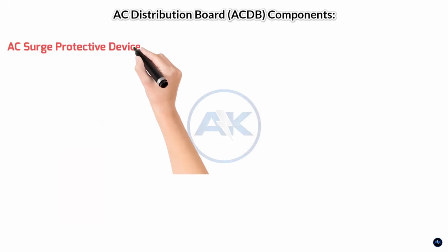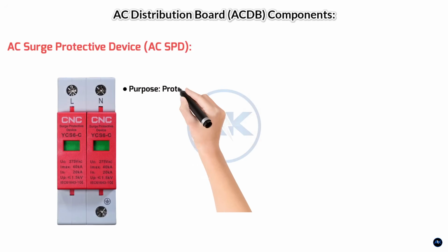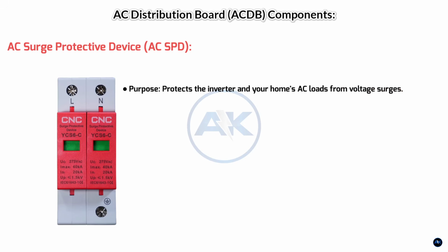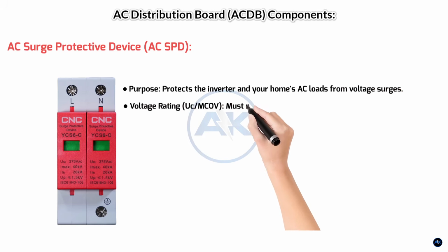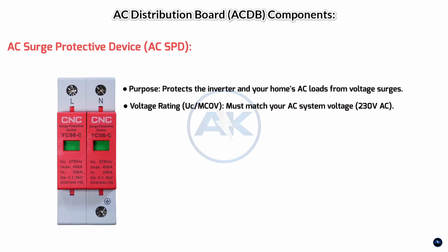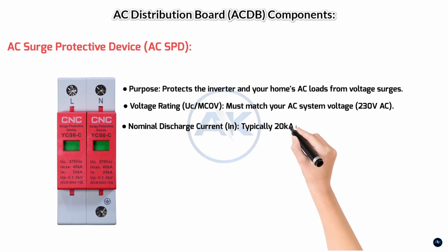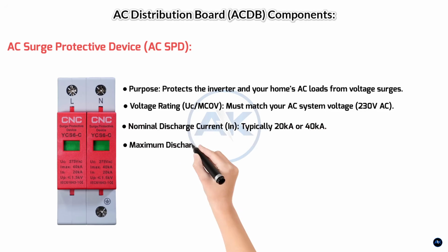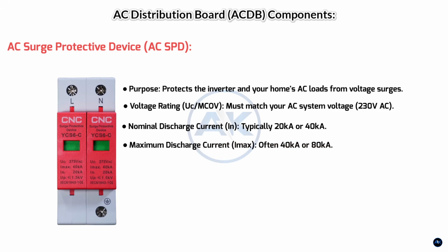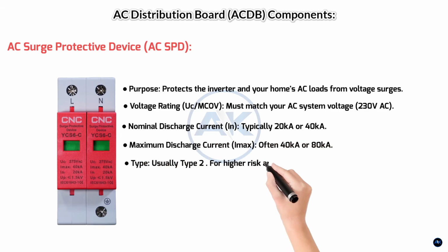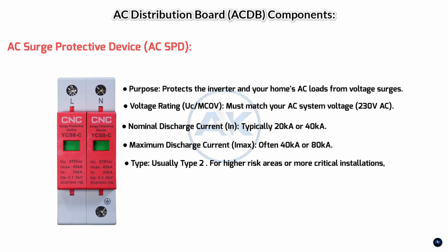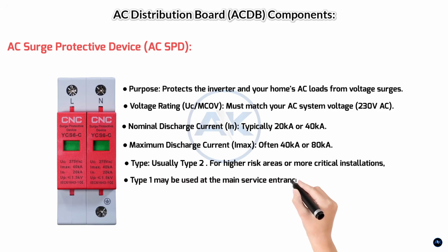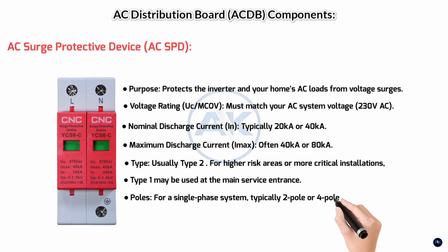AC surge protective device, AC SPD. Purpose: protects the inverter and your home's AC loads from voltage surges. Voltage rating, UC/MCOV, must match your AC system voltage, 230 volts AC. Nominal discharge current is typically 20 kiloamperes or 40 kiloamperes. Maximum discharge current, IMAX, often 40 kiloamperes or 80 kiloamperes. Type: usually type 2 for residential applications. For higher risk areas or more critical installations, a type 1 may be used at the main service entrance. Poles: for a single phase system, typically 2-pole, or 4-pole if protecting neutral and phase.